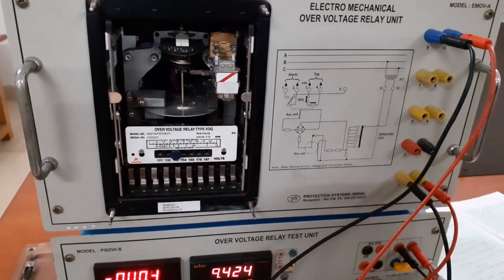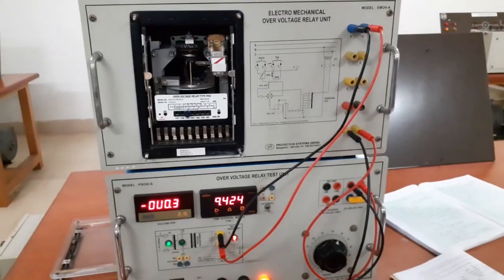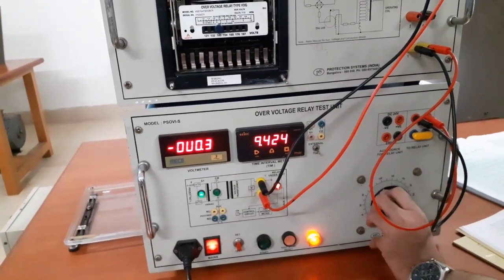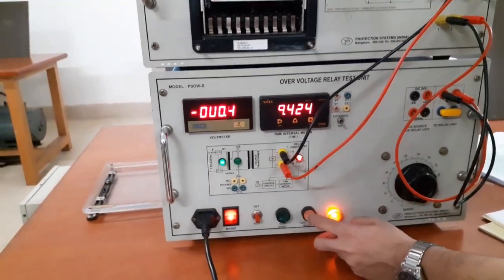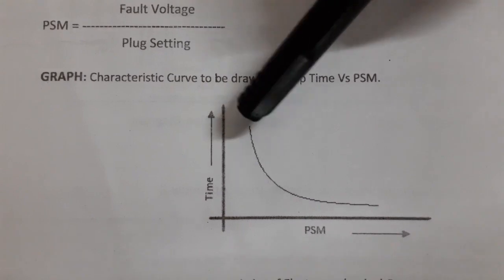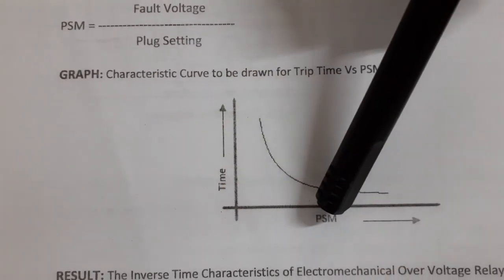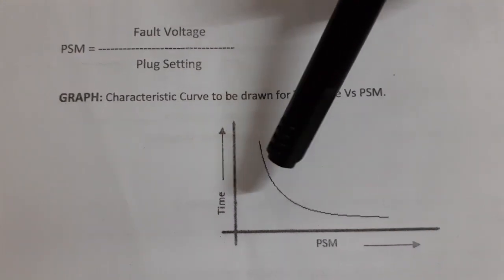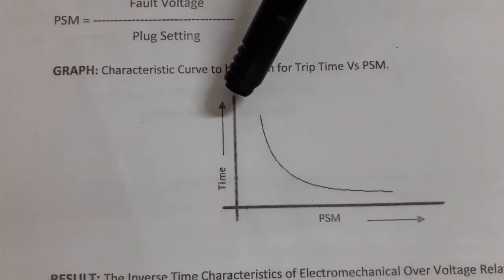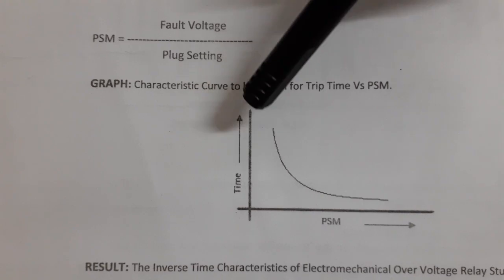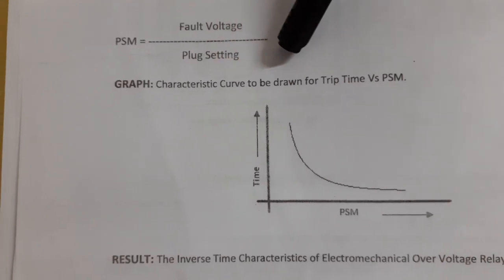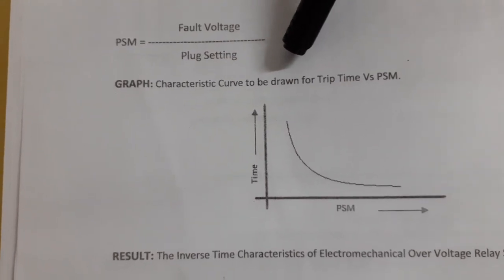Repeat the similar steps for other readings. Turn off the system: first return the dimmer stat to zero, click reset, return to set mode, then turn off the main supply. Finally, you will be able to get a graph of time versus PSM. From this graph, we understand that for a high fault voltage the tripping time is very less — it activates very quickly. On the other hand, if the fault voltage is very low, it takes a lot of time to trip.